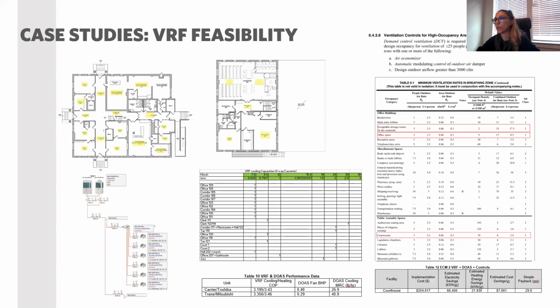So one of the examples, like I mentioned about our typical ECMs, but sometimes we actually get deeper because we saw so many other problems. So this is the same courthouse building, 9,000 square feet. It is a very old, 93-year-old building, but they have already done an LED retrofit, and they replaced their windows to low-E. Over time they had many retrofits, and 13 years ago they also retrofitted their HVAC system to heat pumps. But when I was in the building, they were having problems meeting the set points. Even those heat pump systems are single zone systems, so not every room gets the air, especially if you have not done the TAB or balancing work correctly. So some rooms were hot, some rooms were cold, the air was not distributed properly. So there were so many problems.